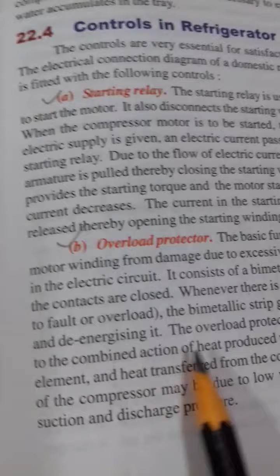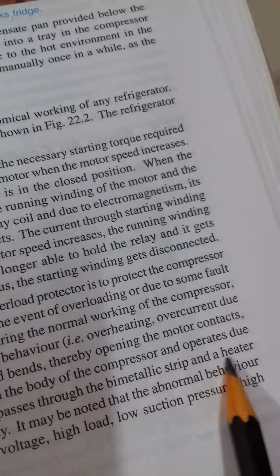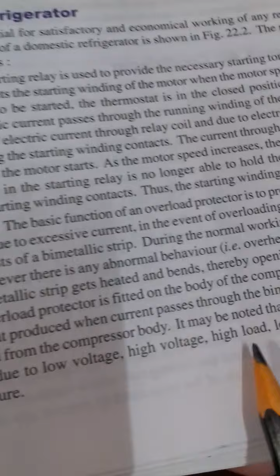The overload protector is fitted on the body of the compressor and operates due to the combined action of the heat produced when current passes through the bimetallic strip and a heater element, and heat transfer from the compressor body. It may be noted that abnormal behavior of the compressor may be due to low voltage, high load, low suction pressure, and high suction and discharge pressure. These are the reasons for which the overload protector is provided.